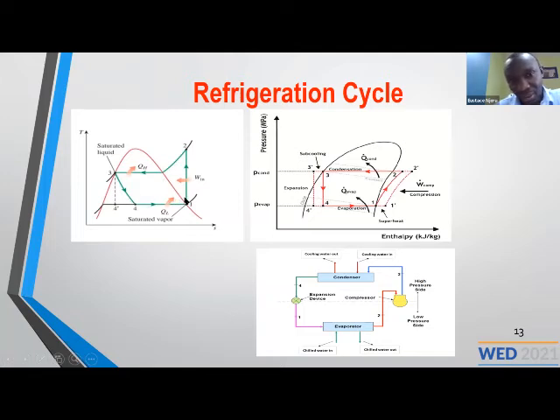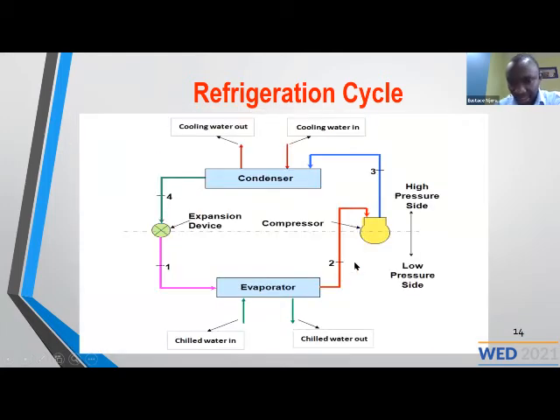Here you can do what we call temperature reset. At the same time, for the compressor, you can get the most efficient compressor, with an efficient motor and compressor itself. From there, you can minimize the amount of energy you are drawing from the electricity mains line. So that's the diagram. That is the schematic diagram of the refrigeration cycle, where you have the evaporator, the compressor, and so on. That's what you have been explaining in the previous part.